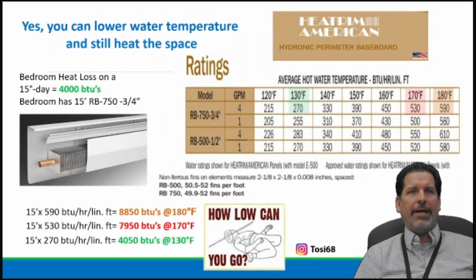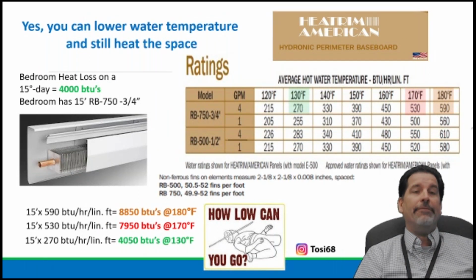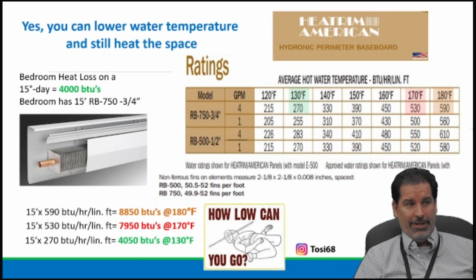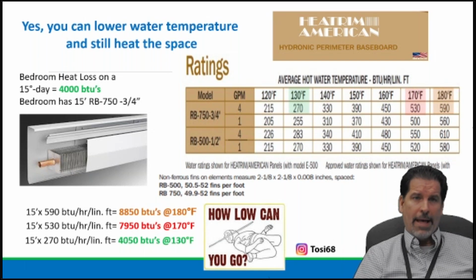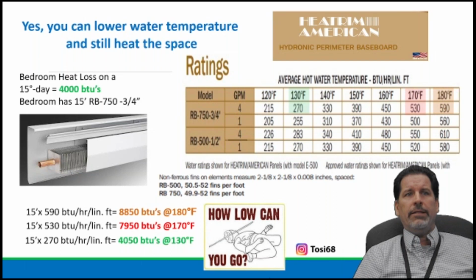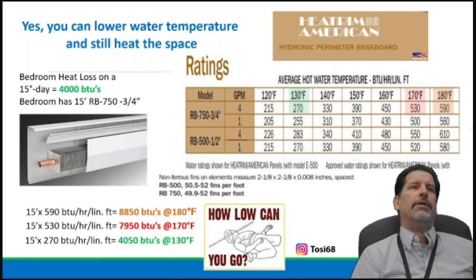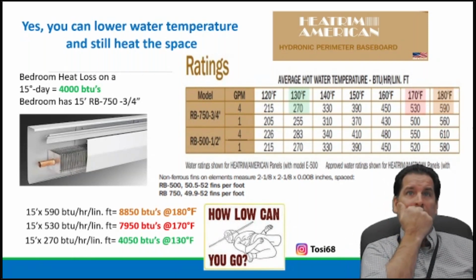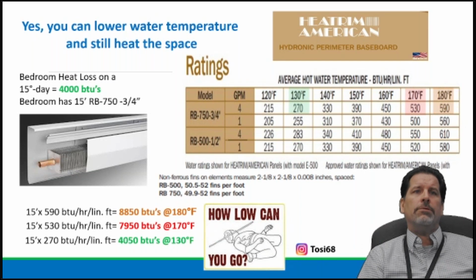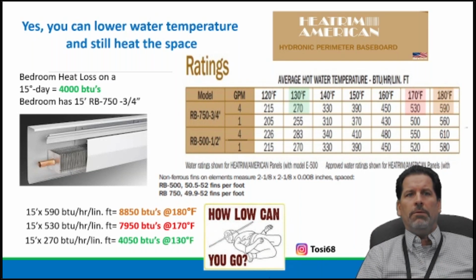If you never knew baseboard has a rating, everything has a rating. Boilers, baseboard, hydrocoils, fin tube, panel rads. I mean, all these things have charts telling you exactly the information that we need if we choose to look at it. So that bedroom's heat loss on a 15-degree day, 4,000 BTUs. There's that 15 foot of RB 750 3/4. Here's a chart, right? This is Heatrim. This is a Sterling product that we represent. It's been around for many, many years. Look at the chart there.